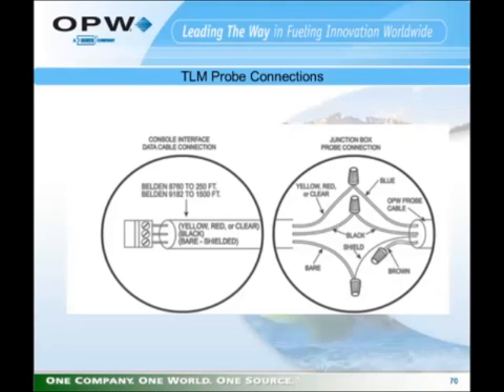Those 3 wires are colored blue, black, brown. The blue wire connects to the cable going into the TLM interface module, the top connector. The black wire connects to the middle connector. The brown wire is capped, and the shield wire connects to the bottom connector on the probe connector on the TLM probe interface module. If the brown wire is connected, you will see multiple probe trouble codes being displayed on the tank monitor. The most prevalent being trouble code 62.